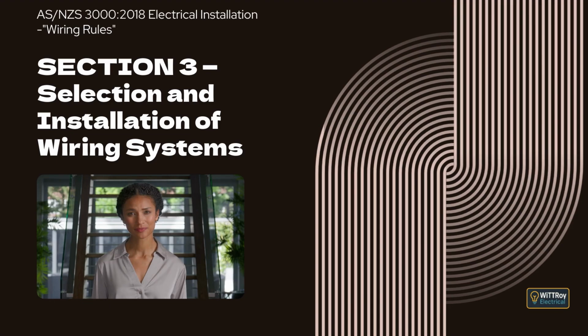This clause explains that alternative and European color systems exist, that care must be taken when connecting imported equipment, and that verification is necessary to confirm correct function and connection. Clause 3.8.3.5, Aerial earthing conductors. This clause states that aerial earthing conductors must be identified at each end of the run, either by the letter E or by the earthing symbol.